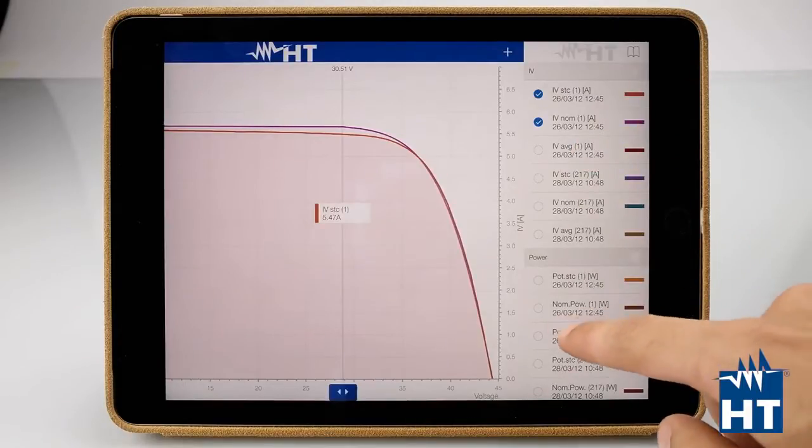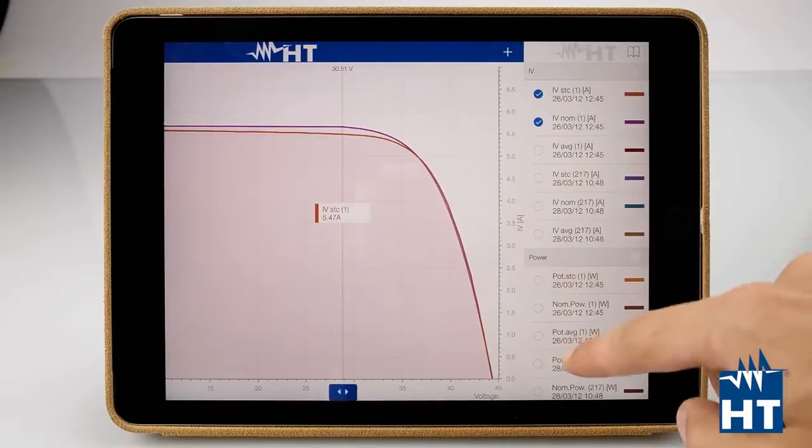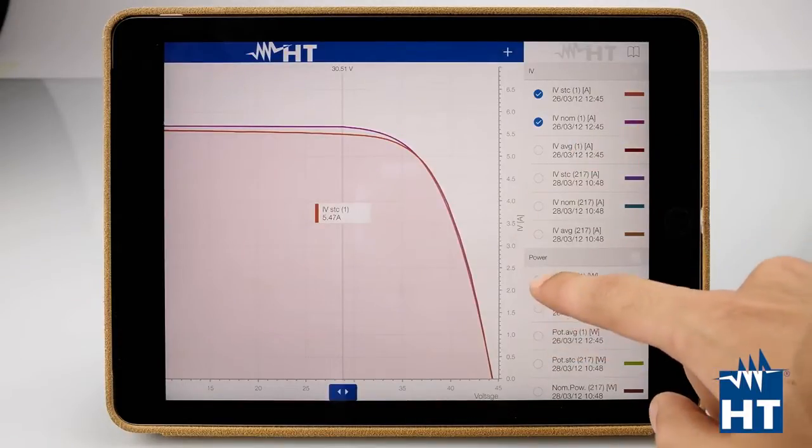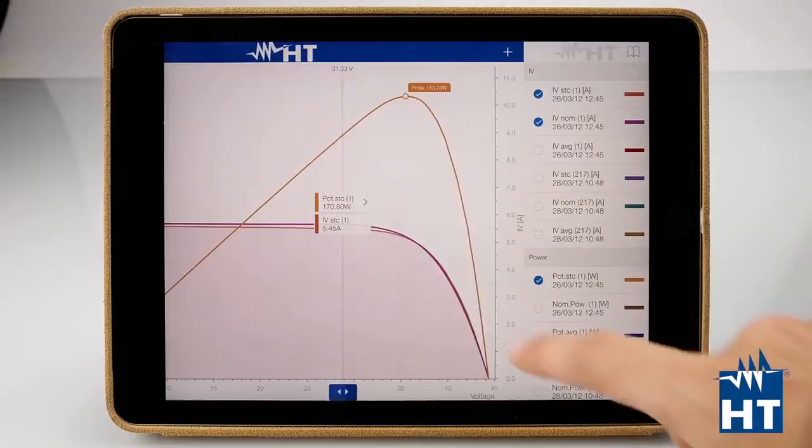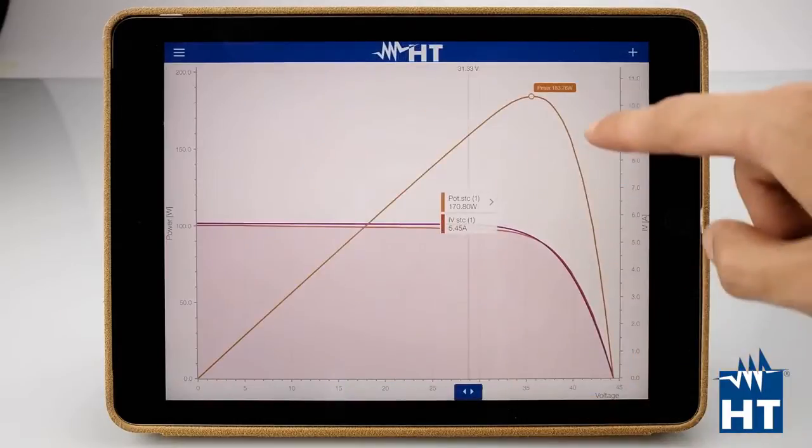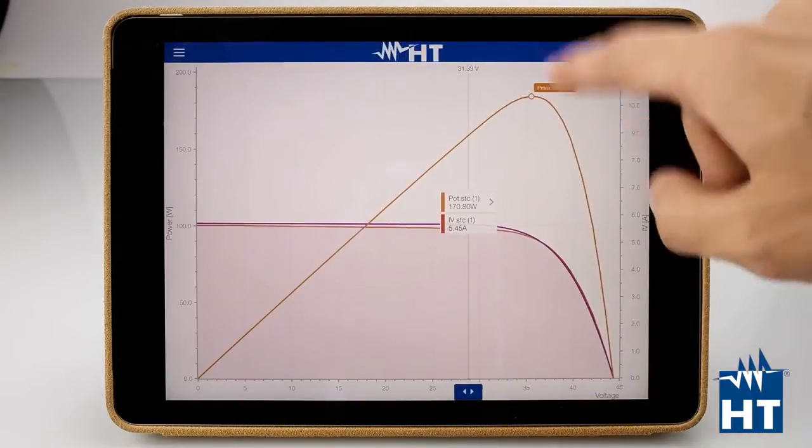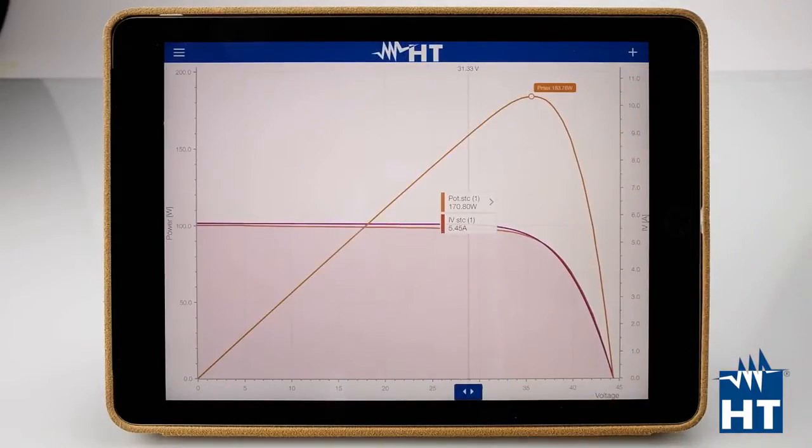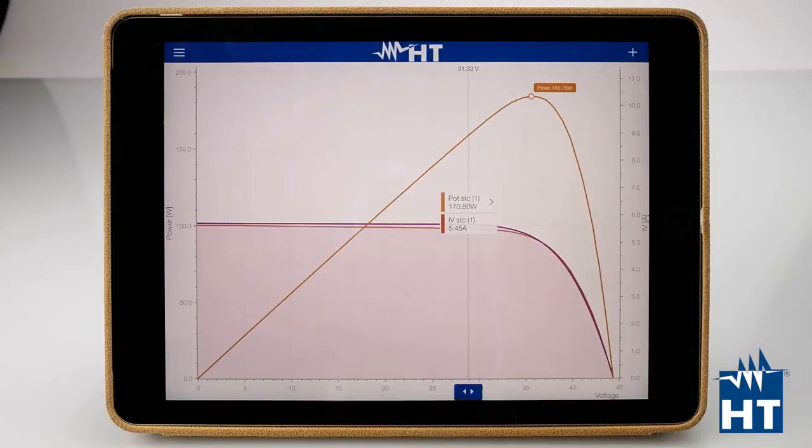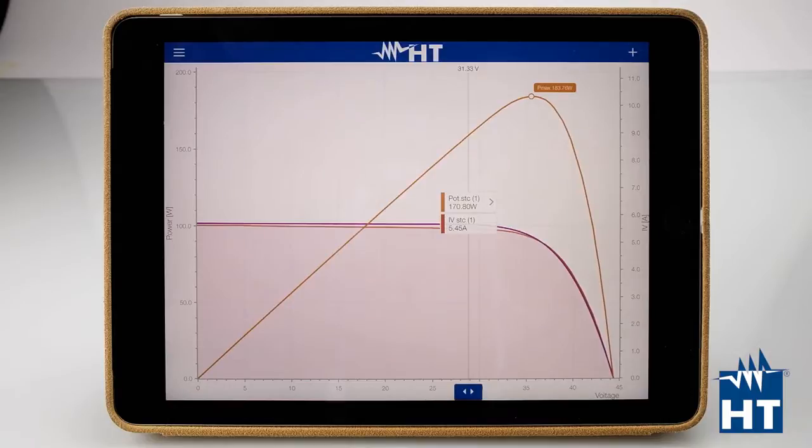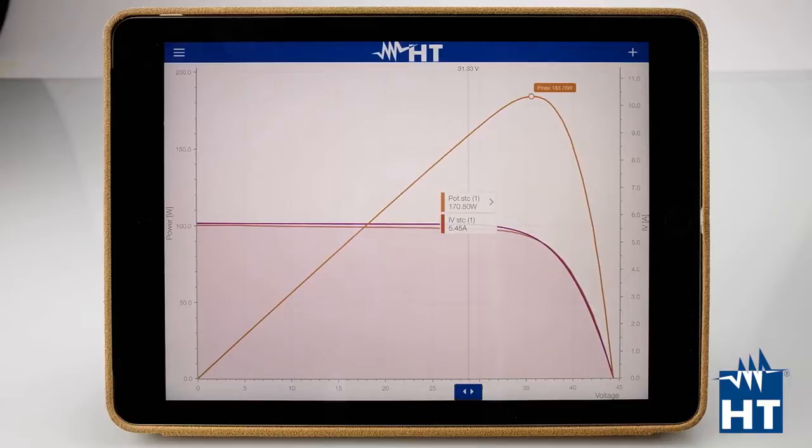Power STC with the maximum power point here. You have the complete data to say something about whether this module is okay, this string is okay, or this plant needs more maintenance or just cleaning the panels.